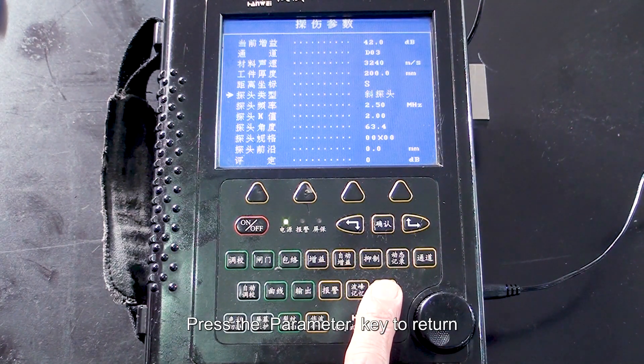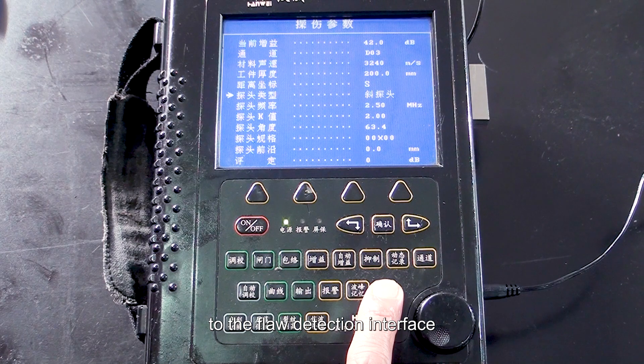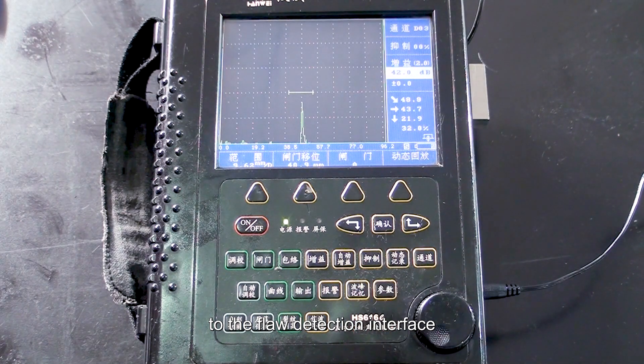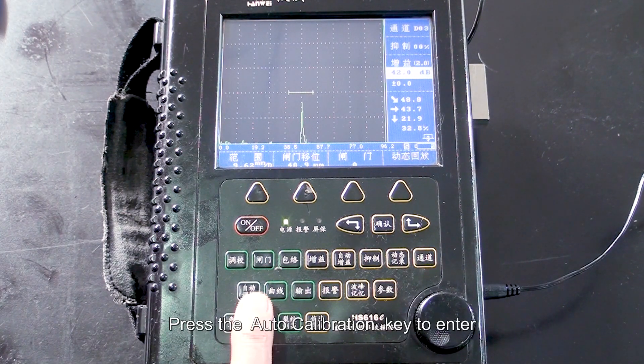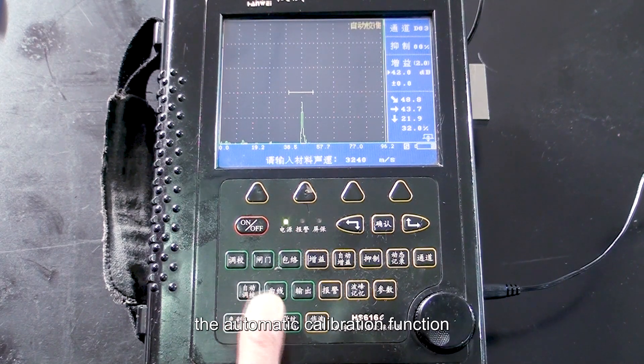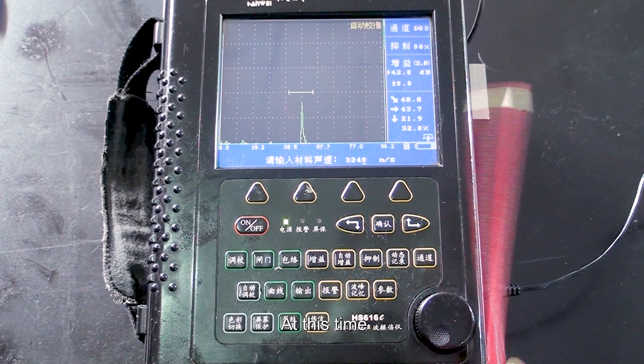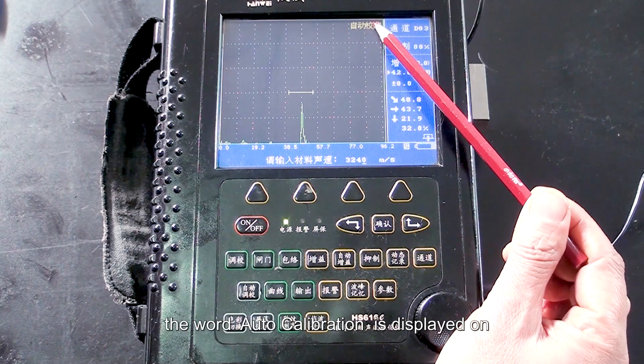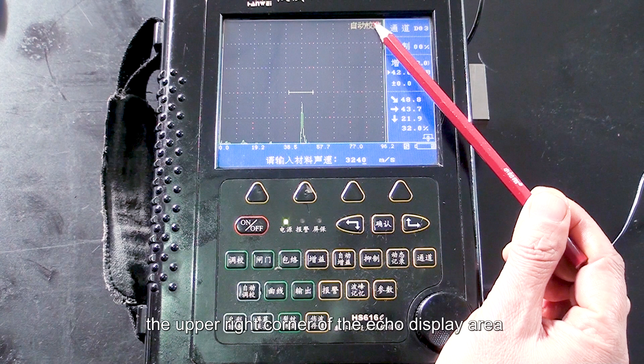Press the parameter key to return to the flaw detection interface. Press the auto-calibration key to enter the automatic calibration function. At this time, the word auto-calibration is displayed on the upper right corner of the echo display area.